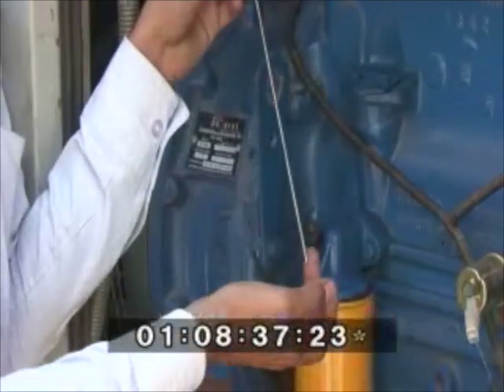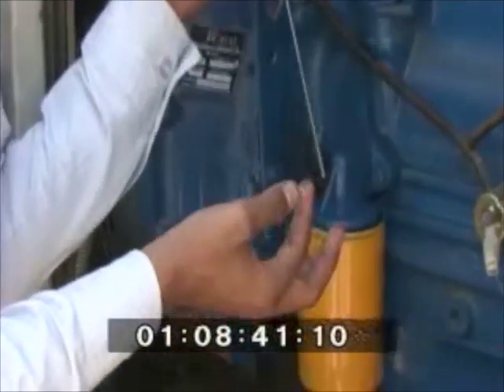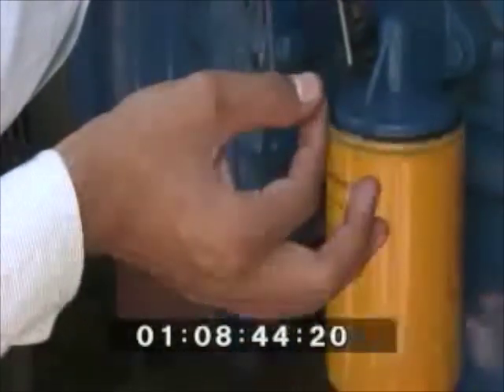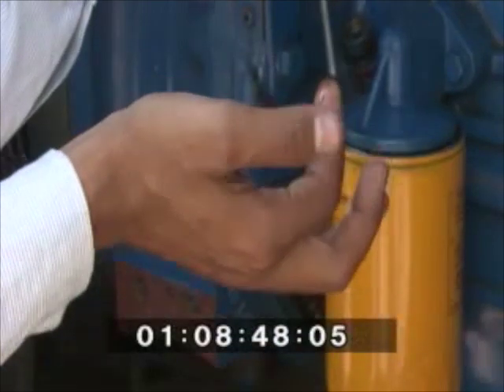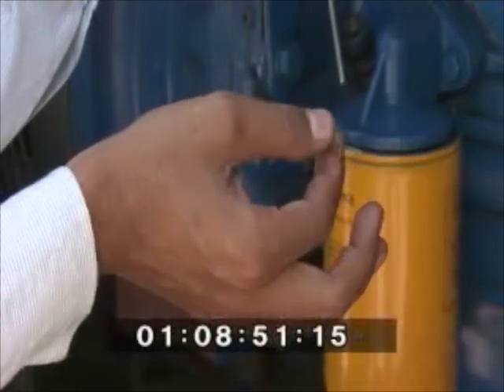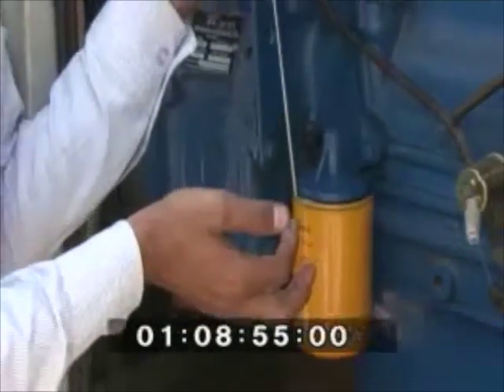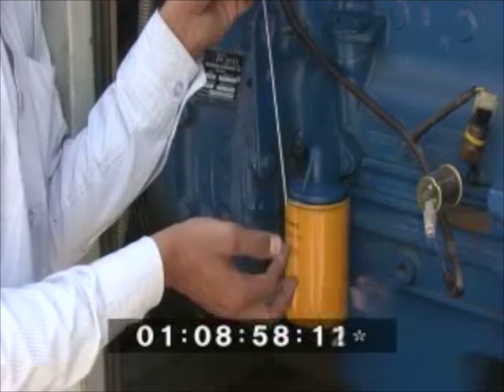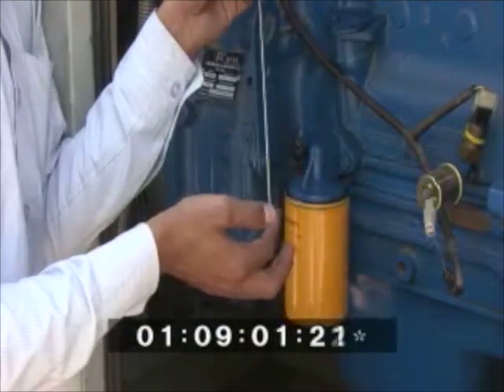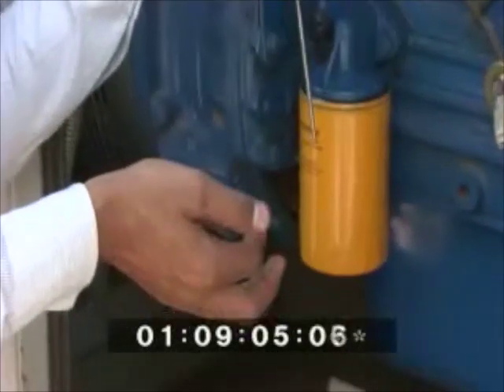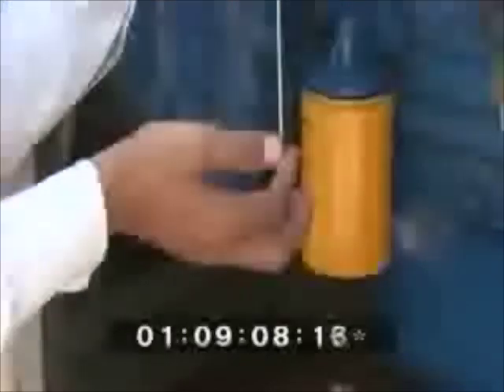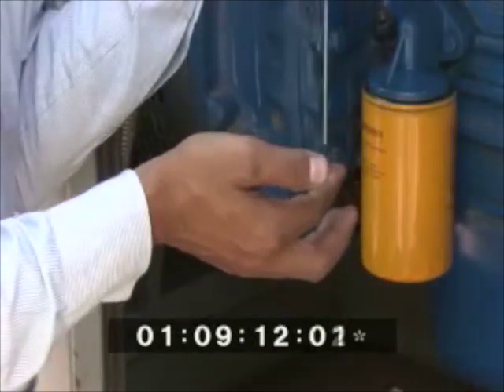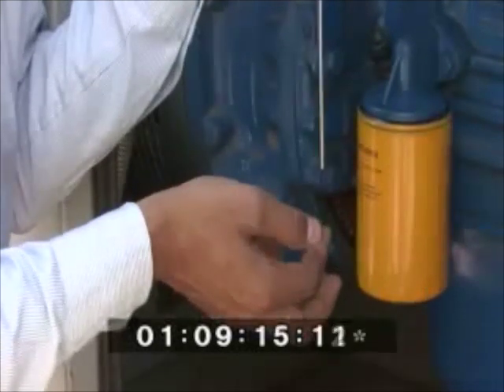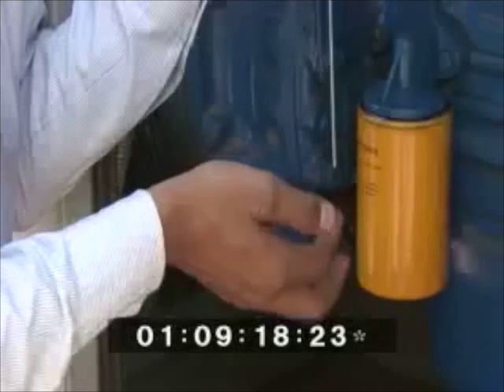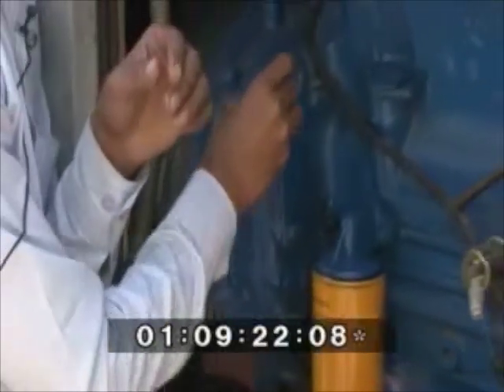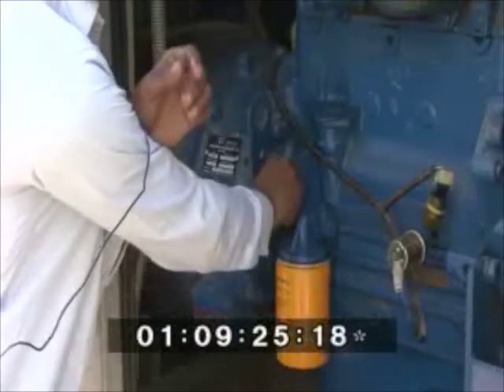Now we will put a few drops of lubricant oil onto our fingers and feel whether the viscosity of the oil is okay or not, and whether it has the lubricating feel. We need to do this checking every 15 days. We need to check for both the level and the lubricating properties. In case the lube oil is less, the DG will not start and the LLOP alarm will get triggered. However, if we still run the DG, the engine will seize.